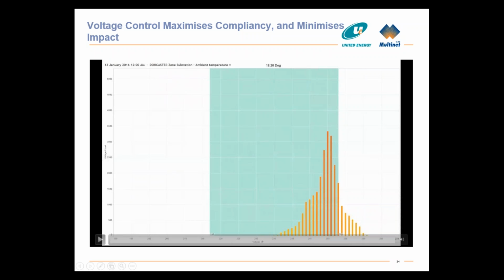I've got a video here with a histogram of how many customers are reporting what voltage on the network. The green block is our compliancy, where the distribution code limits us so customers should not be lower than this or higher than that. We can see we already have some customers higher - this was a very specific hot day that we had.